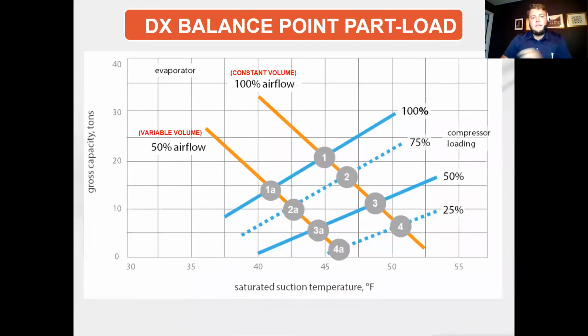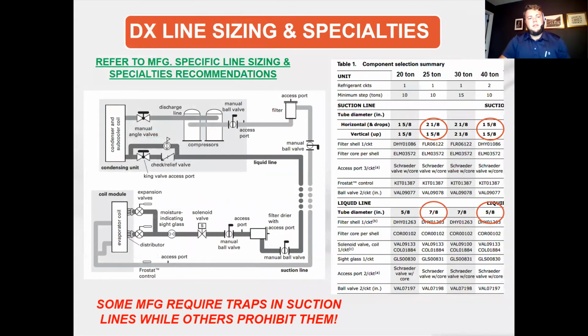Okay. All right, so now that we discussed some of the design fundamentals, and if you have a nice balanced connected system ready to go on your design, as we discussed, it's a different world with the 410A and the microchannels and whatnot. When you go in and start looking at the details of line sizing and piping specialties, even down to the actual installation practices, it's very important to refer and work with the manufacturer that you're picking to lay your design out on. Make sure that you're not just using the traditional rules of thumb, or some of the things we're used to. It's very important to work with the manufacturer and look at their literature and make sure that you're sizing and selecting things correctly for the system that you're laying out.